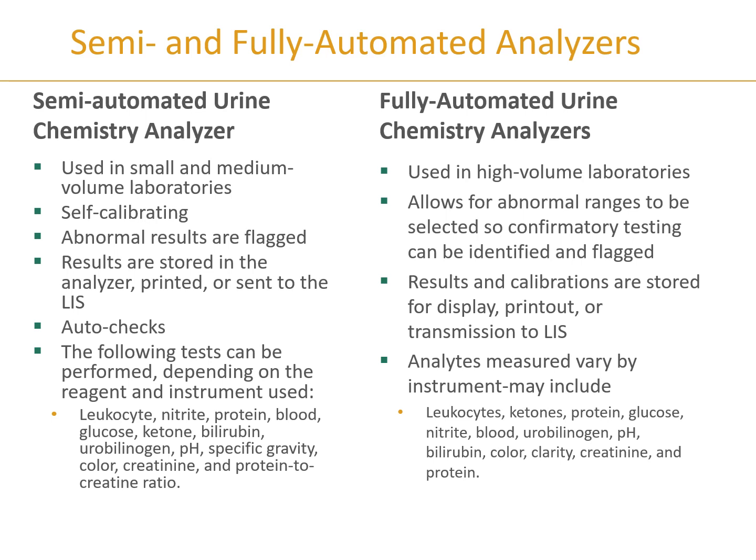Fully automated analyzers are for higher volume labs such as hospital labs, dialysis clinics, and reference laboratories. They allow you to set up ranges and can alert you if confirmatory testing is needed or if microscopics should be reviewed manually. Results, calibrations, and QC can all be stored within the system, printed, or automatically transmitted to the LIS.